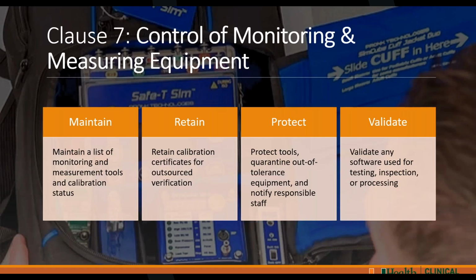And another thing that we didn't know at the time: some of your service providers for test equipment might write in there, before calibration, piece of equipment good to go. That is not okay. If you have an analyzer that has 100 parameters, with different points of testing, every single one needs to be listed on that document. Every single one, not high, medium, low, not PM complete. Every single thing that piece of test equipment can do needs to be listed on that test equipment service. That's the only finding that we had.